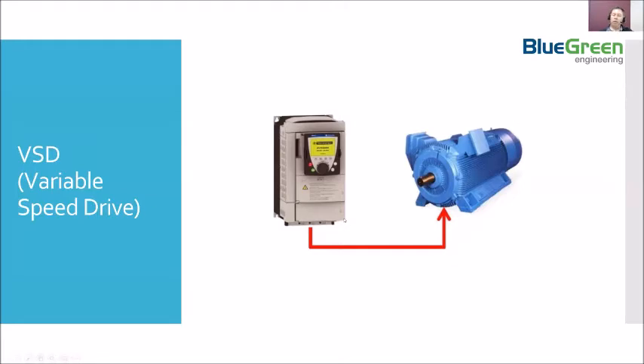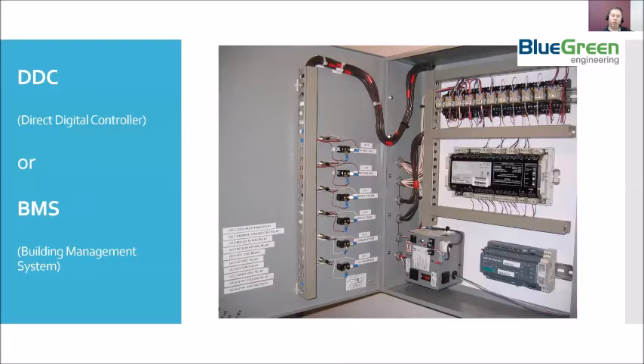And as a simple installation, this can be installed as part of a fix and forget installation, where you install these on condenser water pumps and you open up the restrictor valves to 100%, and then you reduce the speed to, say, 80%, and you leave it there. That's install and forget. But if we want to achieve additional savings in cost and greenhouse gases, we can go to smart controls.